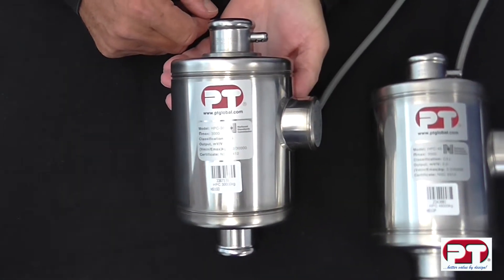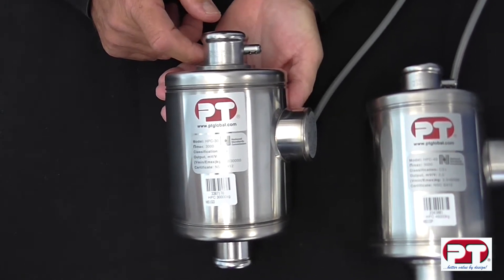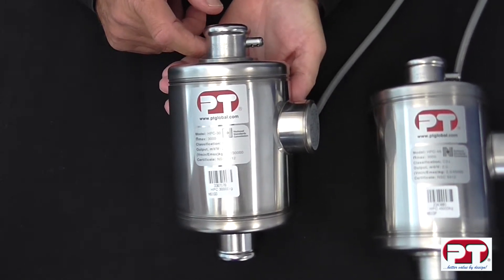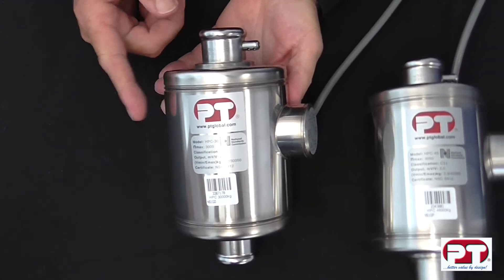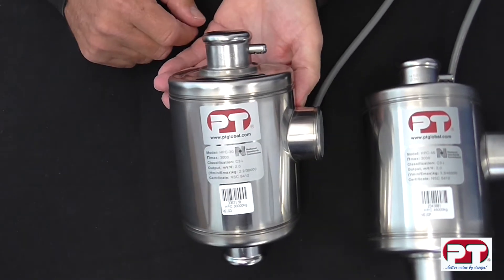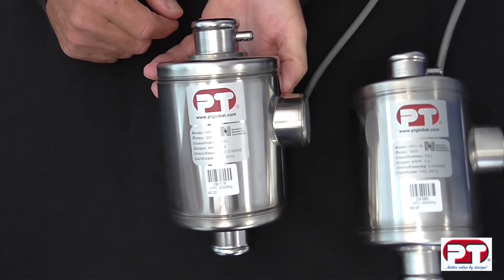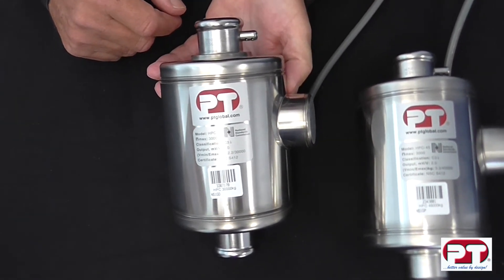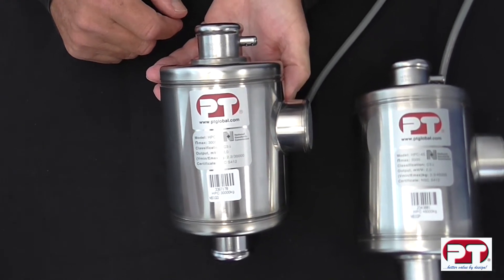The HPC is a state-of-the-art measurement device. Its highly sophisticated and super-sensitive electronics are housed in a rugged, fully stainless steel enclosure. It is fitted with power surge arresters, anti-rotation mechanism, and is inert gas filled for component protection and longevity. The HPC is a true IP68 enclosure rating with greater than 300 hours protection and 1.5 metre immersion.